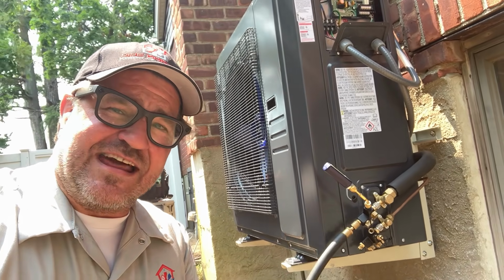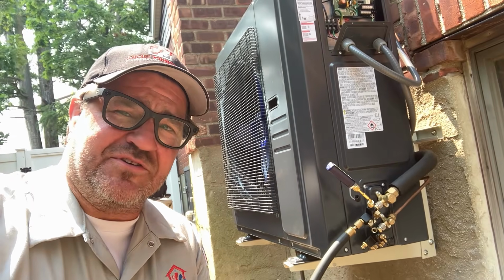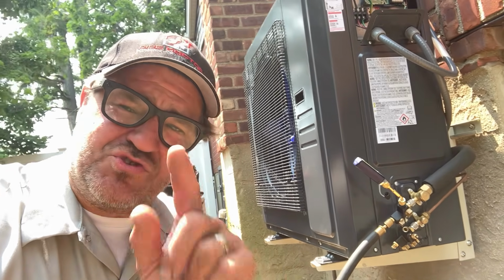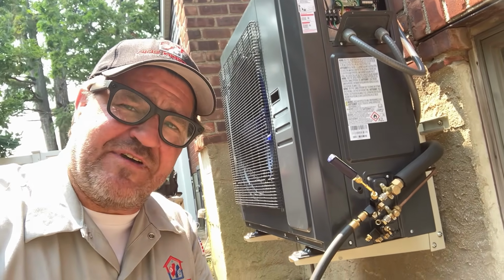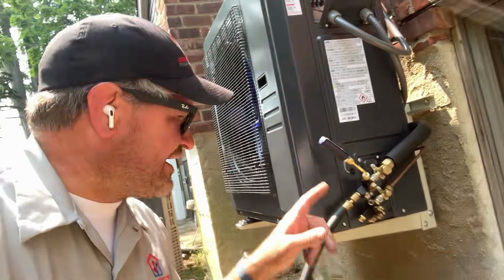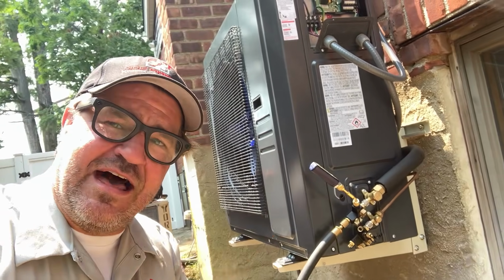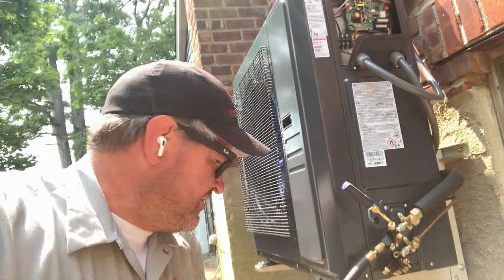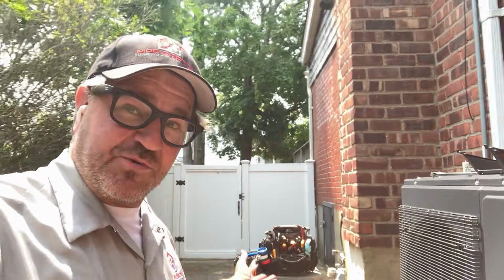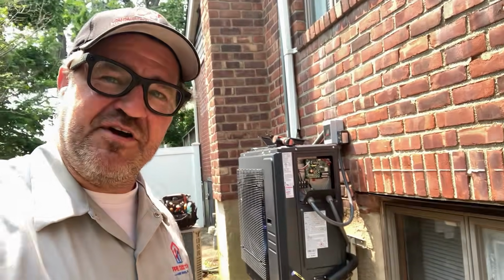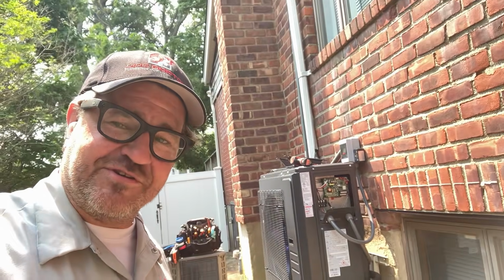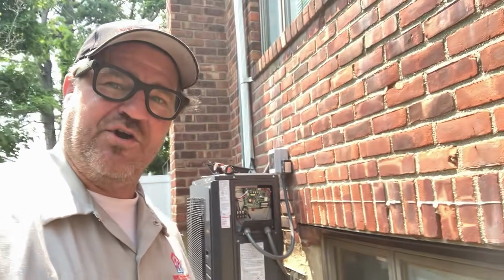So if you're still saying, I pull a vacuum for 20 minutes and call it a day, well, you're doing it wrong. Time doesn't pull a vacuum, performance does. The micron gauge tells the truth, and the micron gauge doesn't lie. Unless, of course, you're using a Navac micron gauge, which sometimes wants to work, sometimes it doesn't. So take the extra time, pull it deep, verify it holds, and your compressor and your customer's wallet will thank you many years down the road.